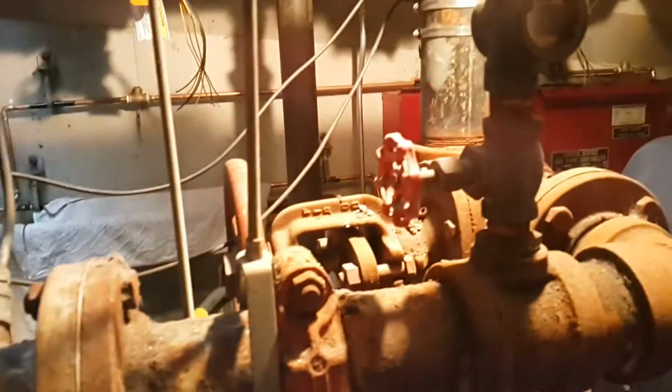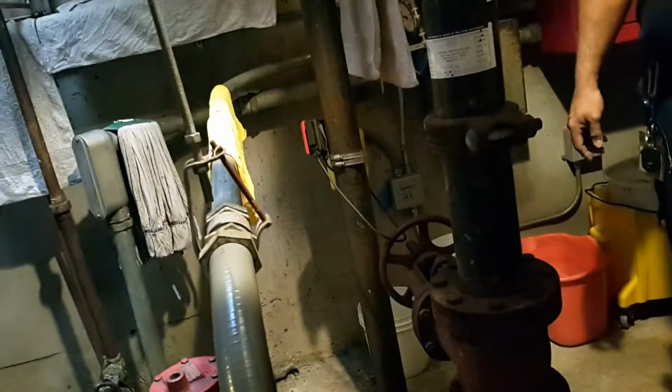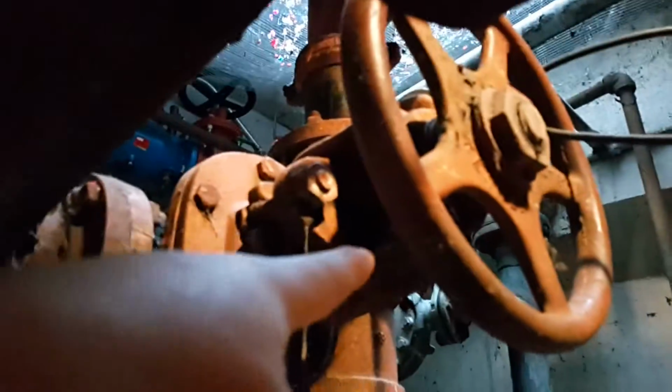So the only two valves that need to be closed are your bypass, because we don't need this. We only need this when we test the fire pump, which we're going to do today also. But I'm going to show you how to do the monthly run first. You said two, so this one and this one, and then that one over here, these two. And this one. So those are the only two that need to be closed. Everything else needs to be open.